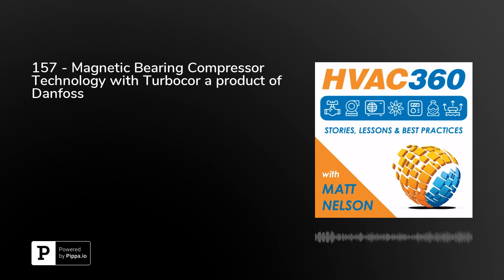When you compare it to a traditional screw with a variable speed drive, you'll still see significant performance improvements, typically in the 5 to 10% range. That's because, even though both compressor technologies are using variable speed drives, the fact that our compressors do not have oil offers significant performance improvements in terms of heat transfer. Okay, excellent.